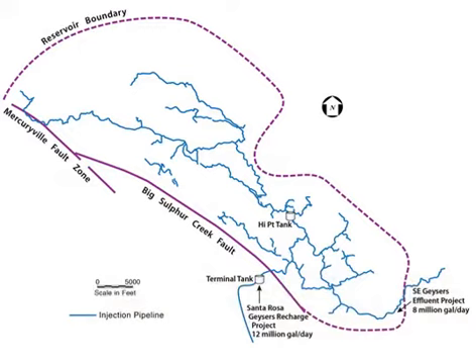Here is a map of the injection pipeline network for the geysers. Note that there are 3 main sources of injection water: the reclaimed water pipeline from Santa Rosa, the effluent pipeline from Lake County, and steam condensate from the geothermal power plants. At the geysers, there is a network of over 120 miles of injection lines and over 35 injection wells. Calpine has about 15 miles of piping to about 16 injection wells dedicated to receiving the water from Santa Rosa.